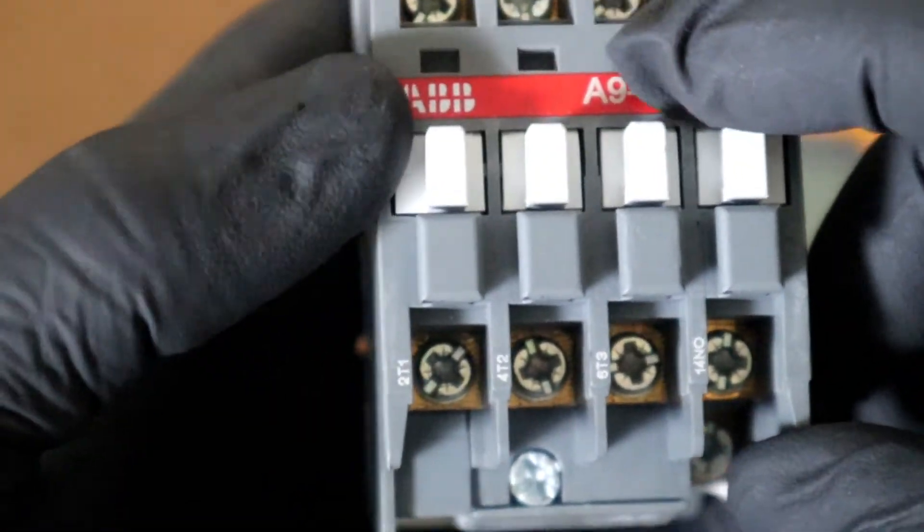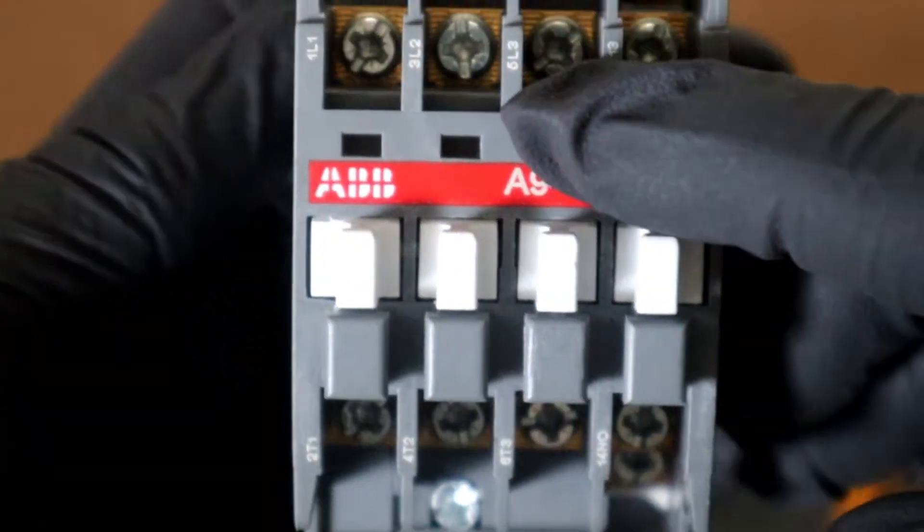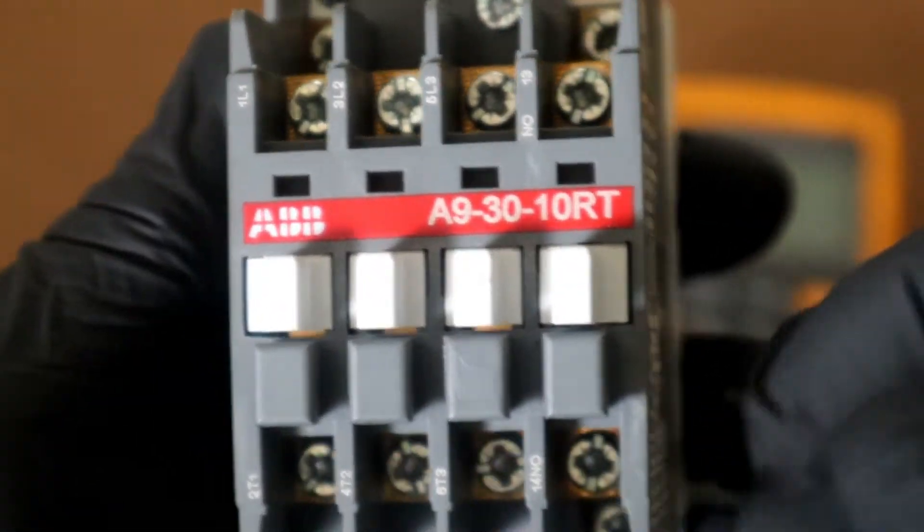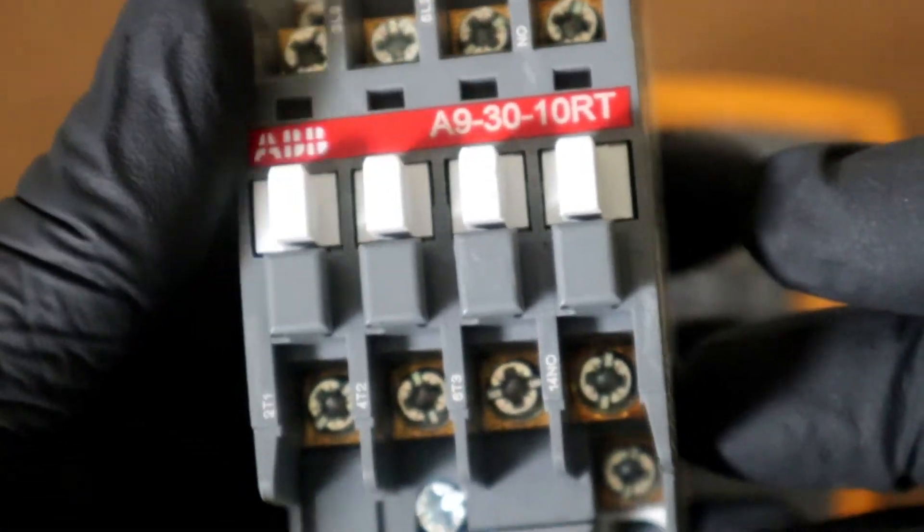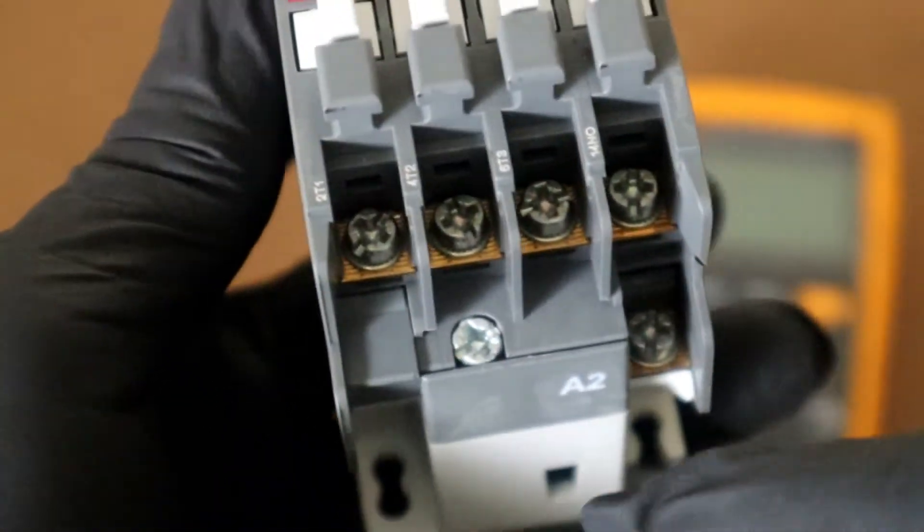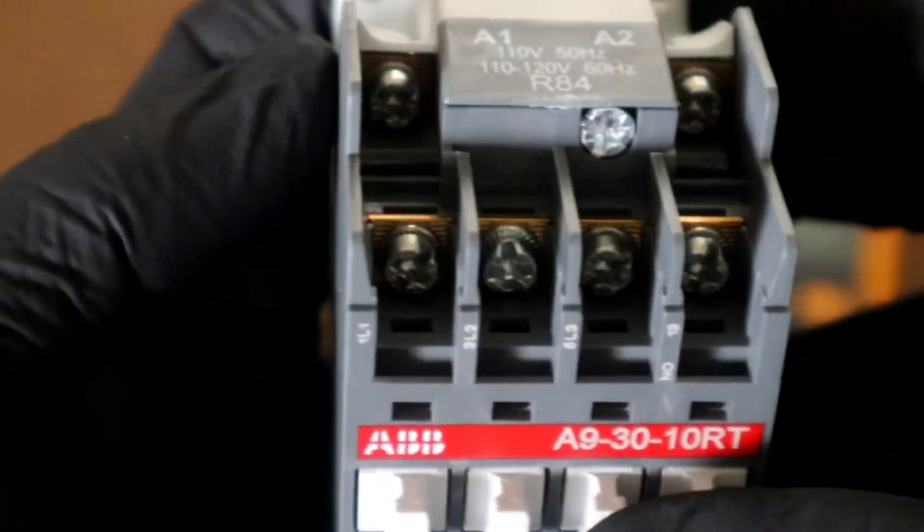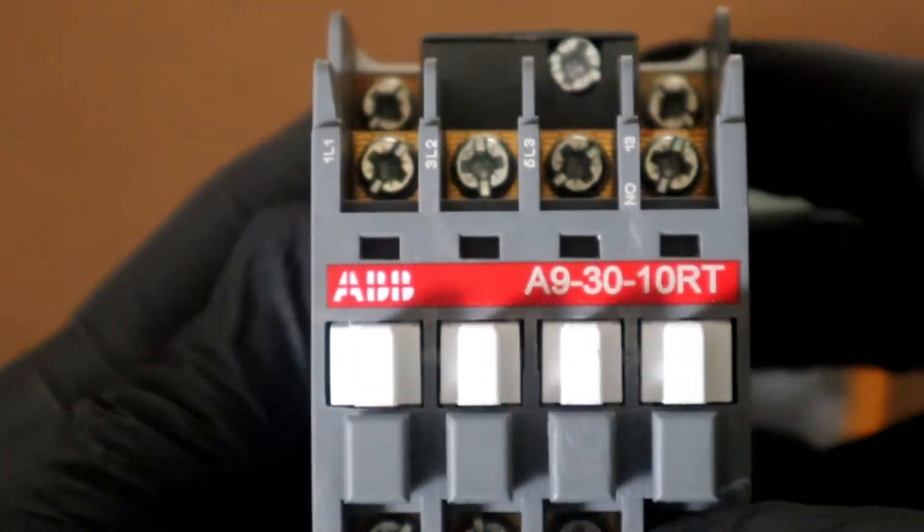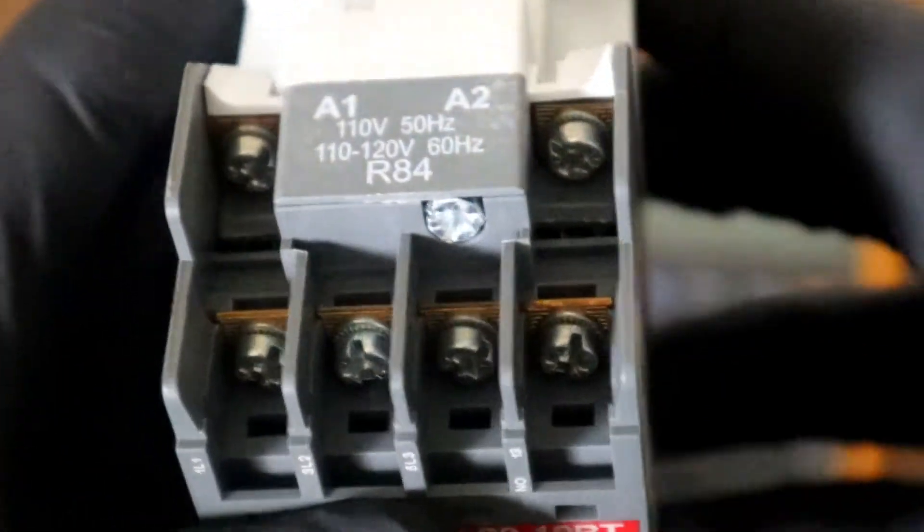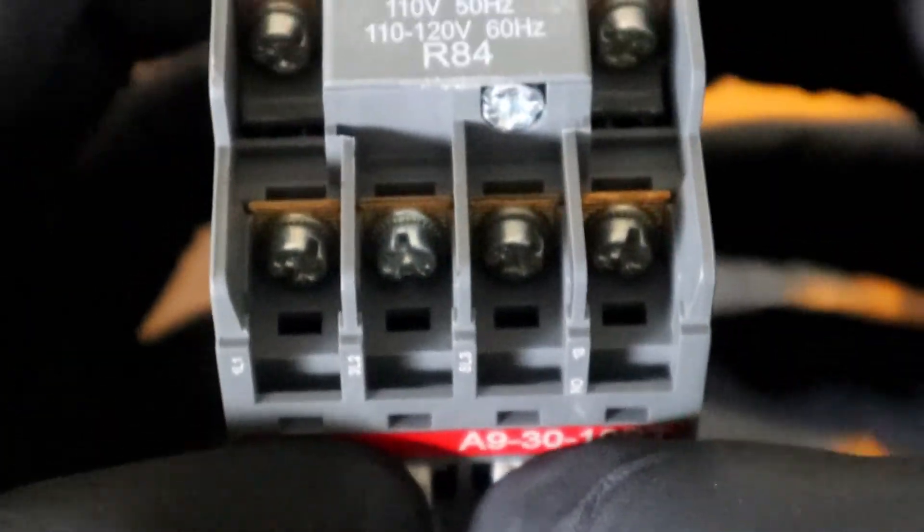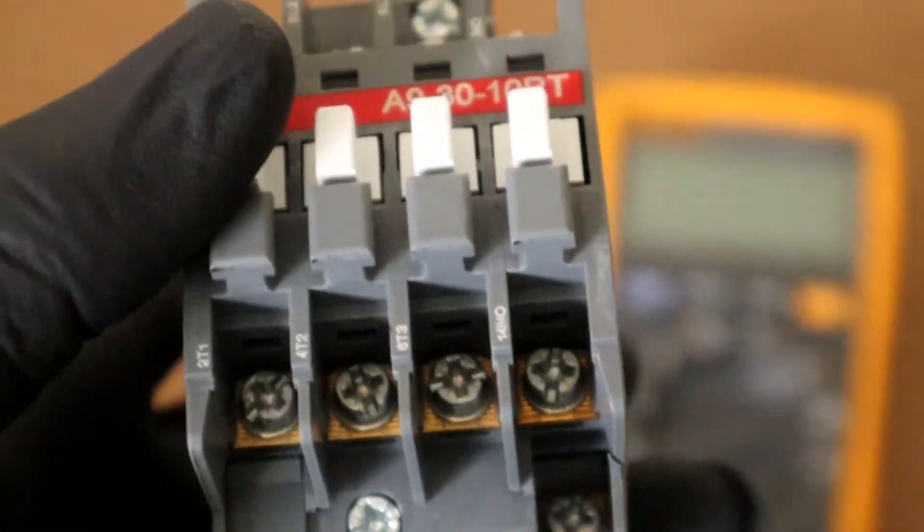These high current contacts can fail in an open position, burnt or melted as a result of a contactor being undersized or a result of a shorted load creating a high current situation. We have many different instances which can cause a contactor to fail. As well as dust, dirt can prevent the complete operation of our contactor and many more factors.